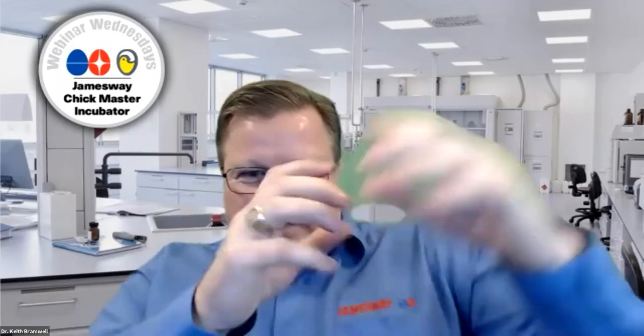What the pilot does is it's measuring the shell temperature of 4 eggs around it. And so we've got numerous devices in there that'll measure 4 eggs each. So if we have a strain that either produces less heat, or smaller eggs or bigger eggs, and the heat has changed one way or another, then it'll adjust that air temperature in there to maintain that shell temperature. So that's how we learned that.